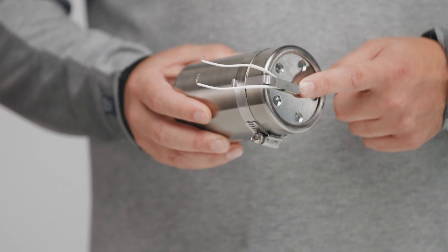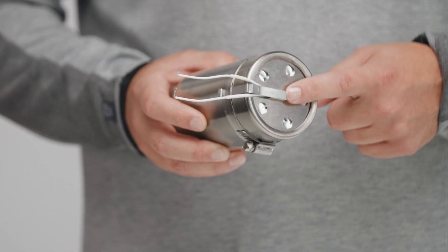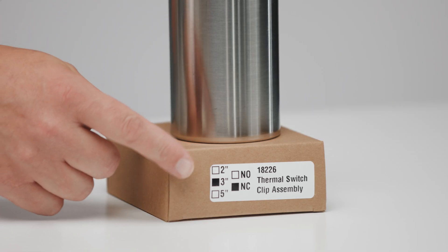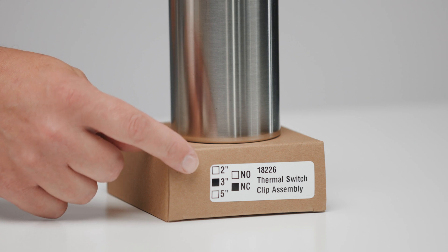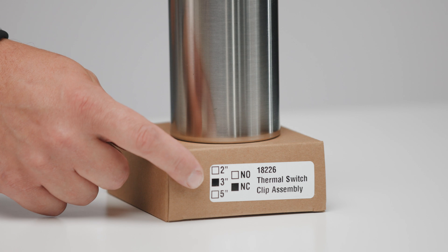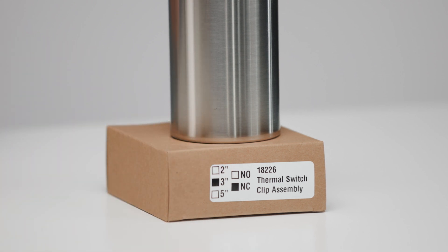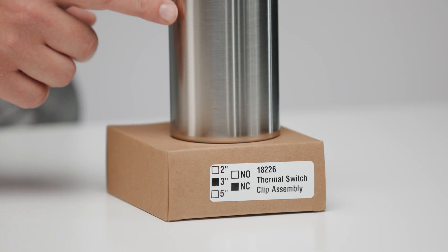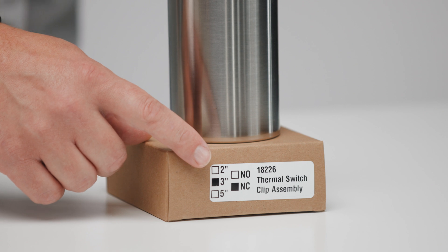The switch itself is rated at a specific temperature and will be activated when the temperature goes over. Before opening the box, you want to look at these two critical pieces of information. The first tells you the diameter or size of the pipe, and the second is whether the switch is a normally open or normally closed switch. For example, this thermal switch assembly is rated for a three inch pipe and is a normally closed switch.